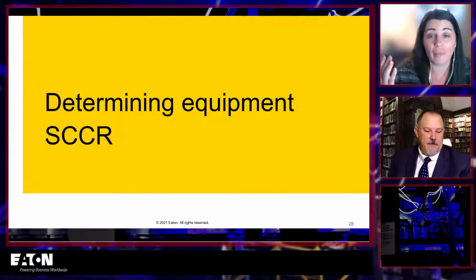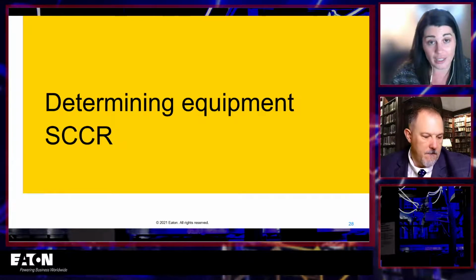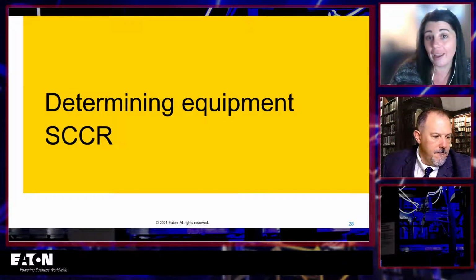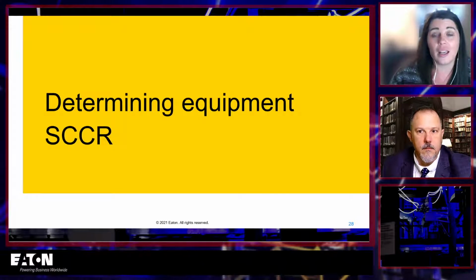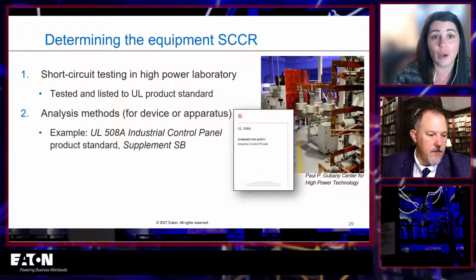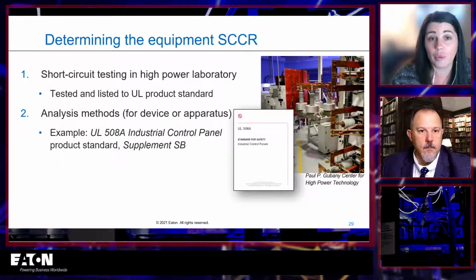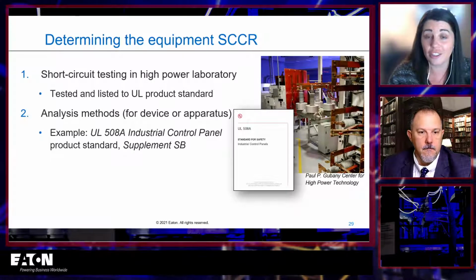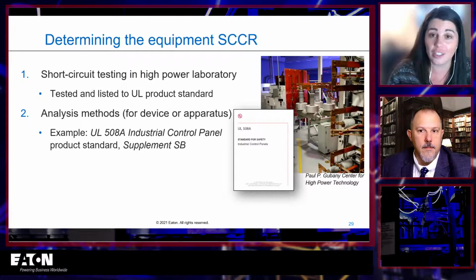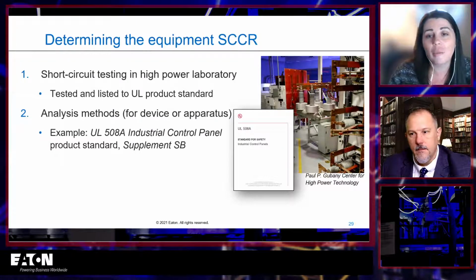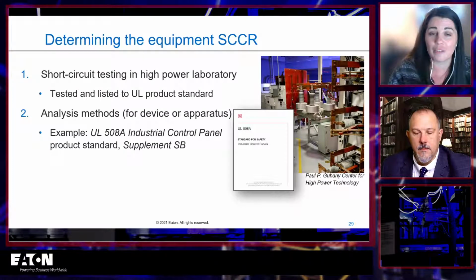All right, so now we'll actually talk about how we determine equipment SCCR. There are 2 main ways that we do this. If you go to the next slide, you'll see the most common one is probably short circuit testing in a high power laboratory. So you build a piece of equipment, you ship it to UL, they zap it with a ton of current. If it doesn't create a shock, fire, or projectile hazard, congratulations, you have a short circuit current rating for your piece of equipment. Obviously it's a little bit more complicated than that. It's to a specific product standard, but more or less that's how it works.